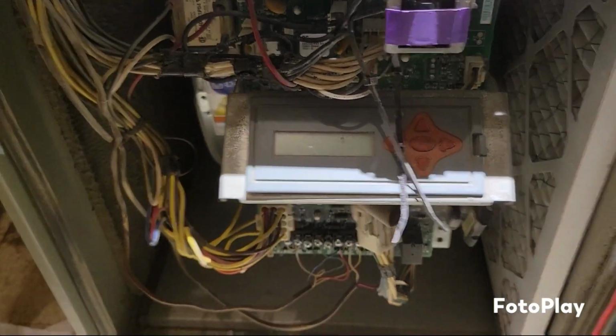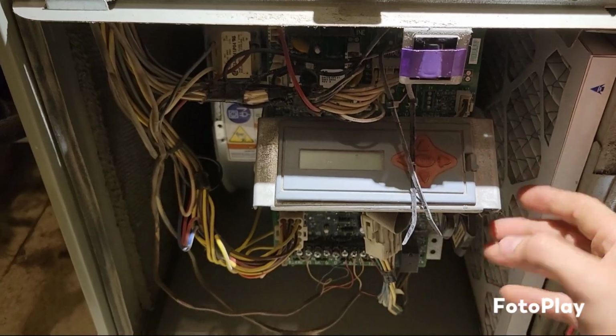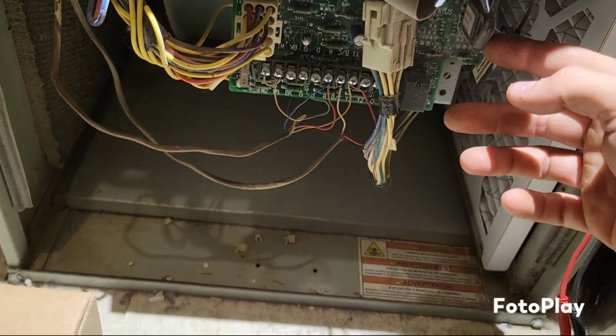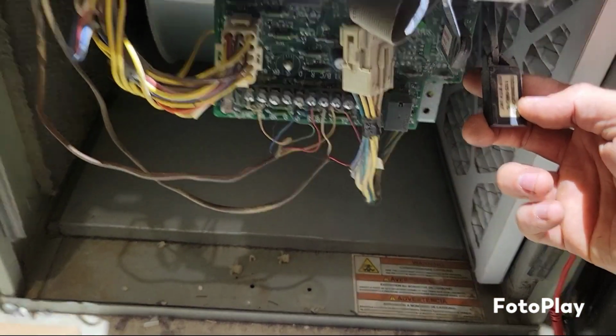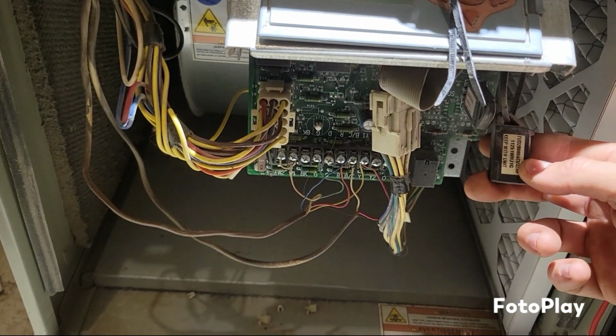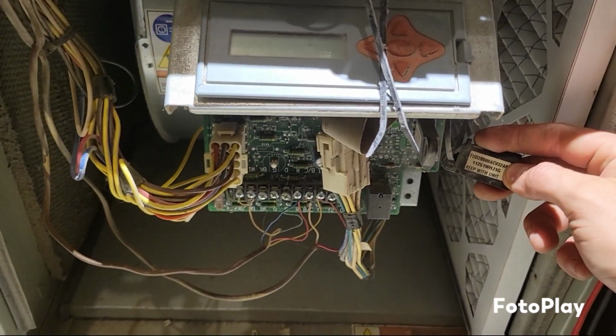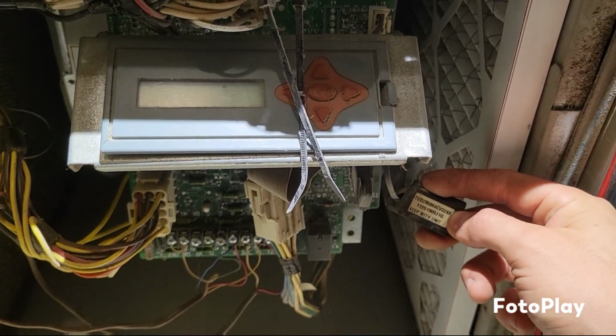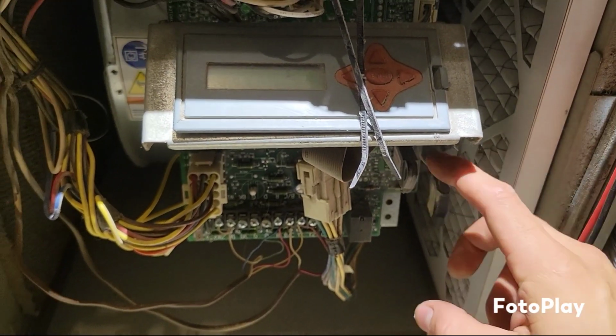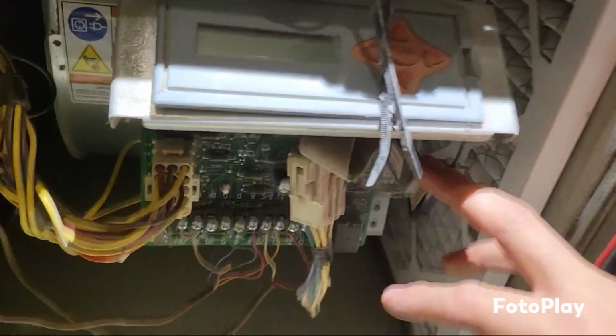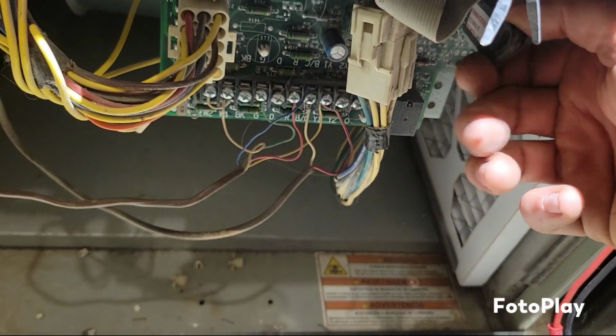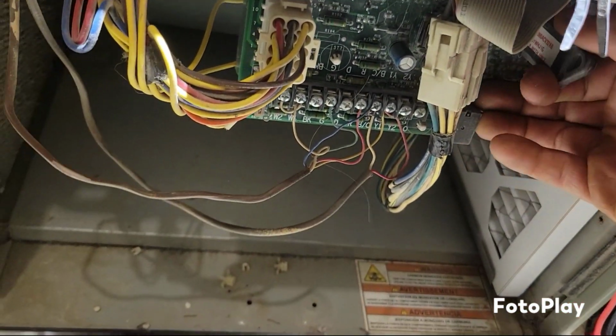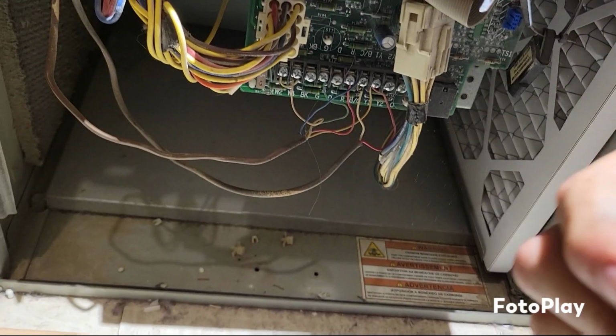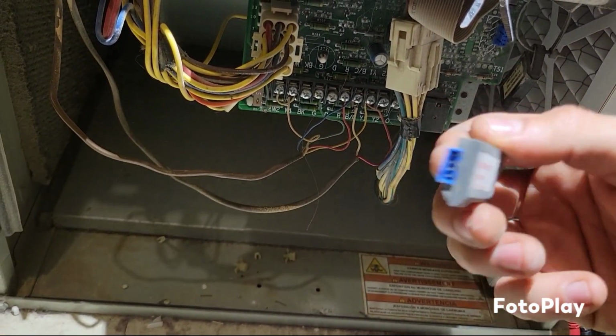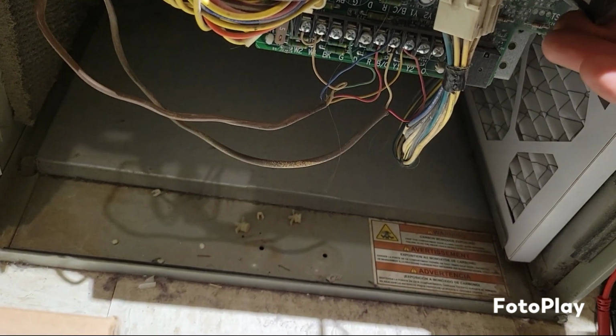So in here, there's this module right here, and it's got a chip right here in the bottom. It's a code chip. So this pertains to this particular board in this particular furnace. So you'll see that it's going to match the model and serial number. Usually the model and serial number of the unit will match whatever is in this particular chip area. And all it is, you literally just pop this in right here. It's just the prongs you see right there, and it goes right back in here.